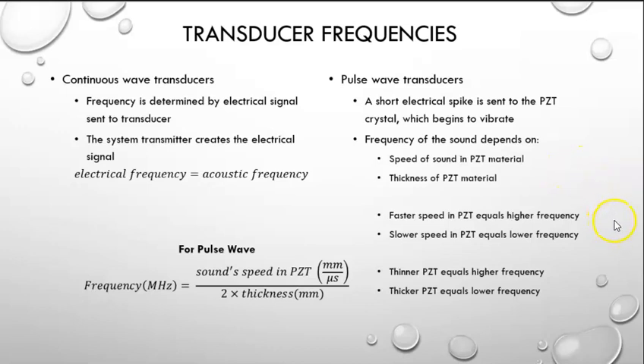So if we get a PZT material with faster speed, stiffer, we get a higher frequency. Remember, that's also going to give us more impedance differences. If we get a PZT material with a slower speed, we're going to get a lower frequency. If we have a thinner PZT crystal, we're going to get a higher frequency, and then a thicker PZT crystal is going to give us a lower frequency. For pulse wave ultrasound, this is an equation we can utilize to determine the frequency of the transducer. It is the speed of sound in a PZT material divided by twice the thickness of the material. That gives us a frequency.